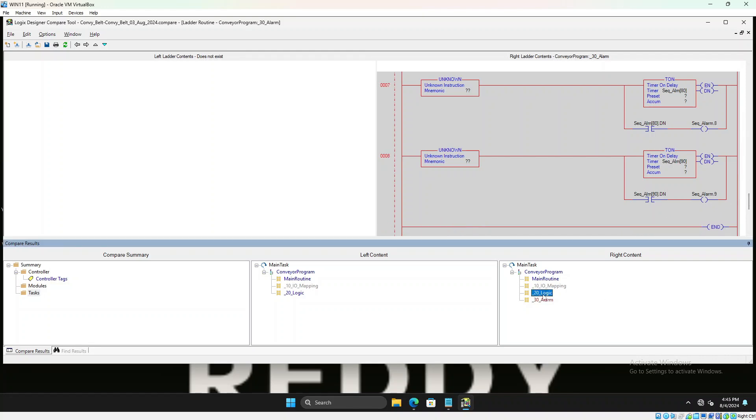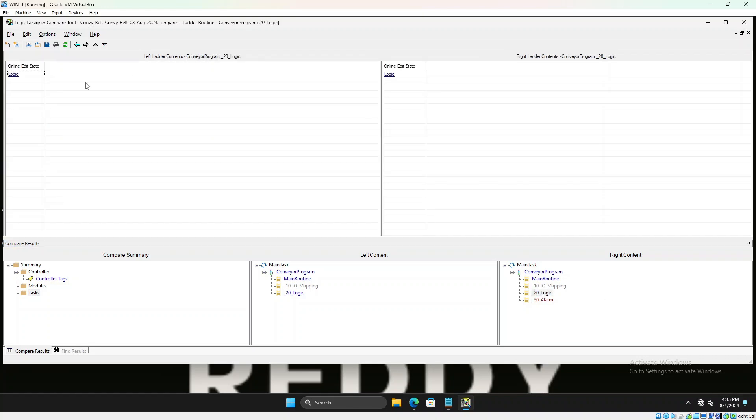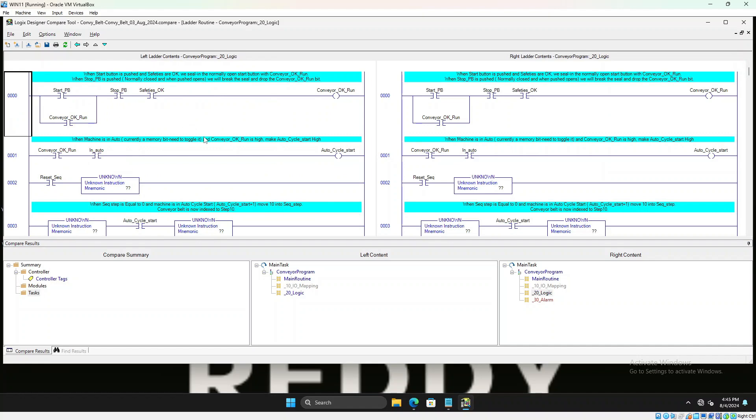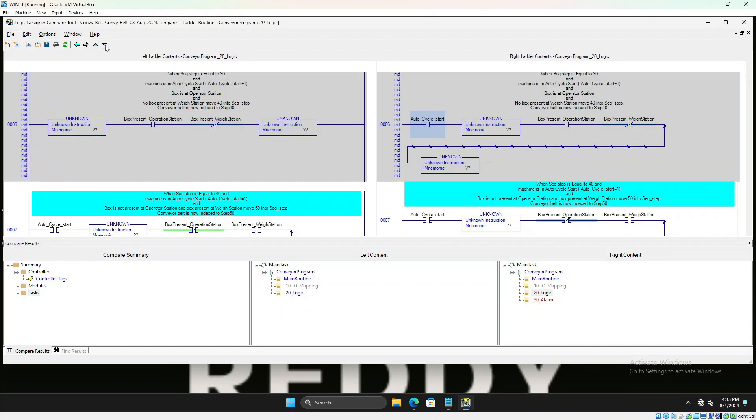And then let's see what's different in this one. If you look at the logic, you could go to the next differences like this. You could see there is one rung different which is missing an auto cycle start. Somebody added an auto cycle start on this one instead of the left one. You know why we are getting unknown instruction? Seems like the equal to instruction EQ instruction is not picking. That could be related to the new firmware revision.